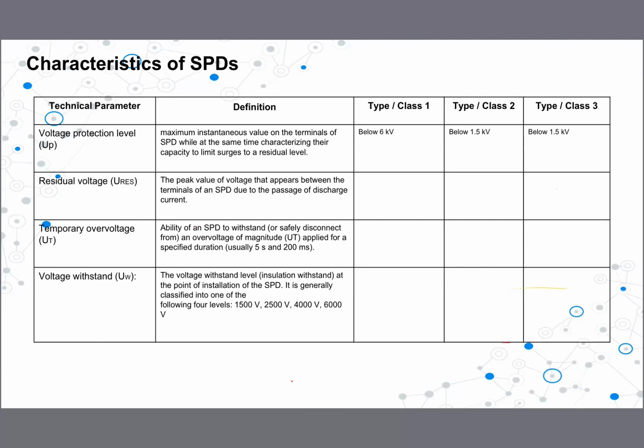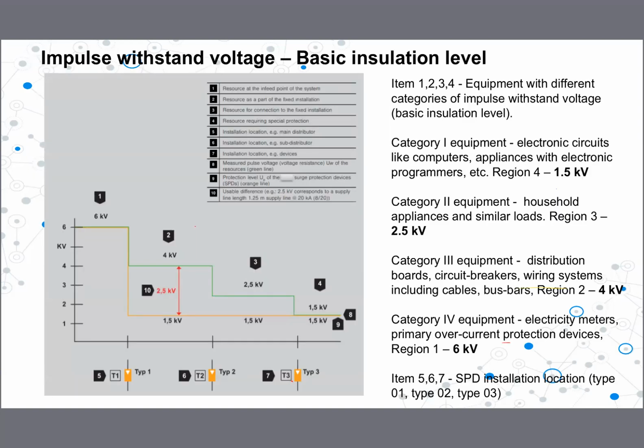Then voltage withstand level, right? What is the insulation level corresponding to the surge protection devices is denoted by the voltage withstand level. Then let's look at what impulse withstand voltage or basic insulation level is. As I explained earlier, if you take electrical components from the start point to the end point of the electrical system, we can divide this equipment into 4 categories. First one is category 1 equipment, right?